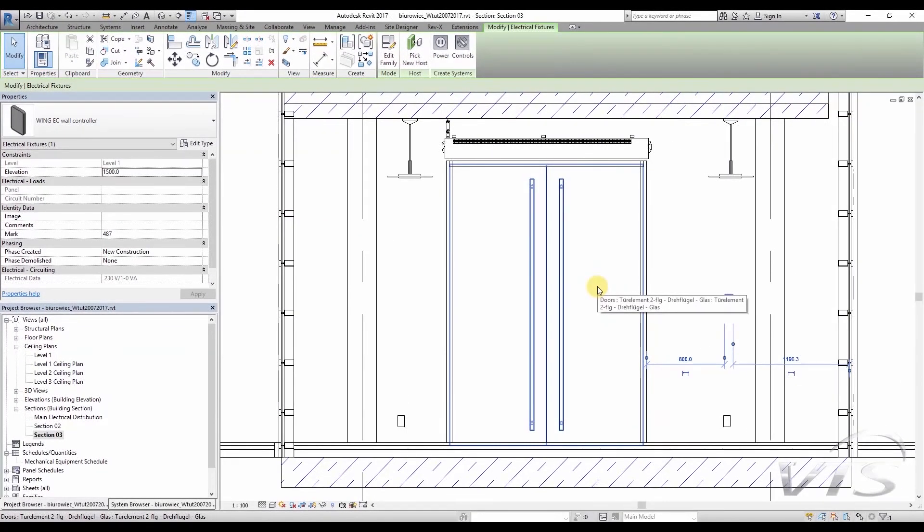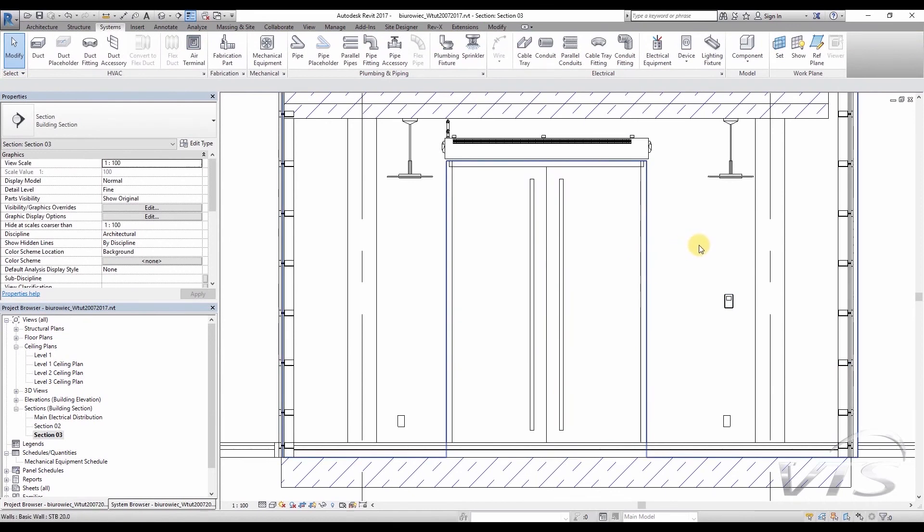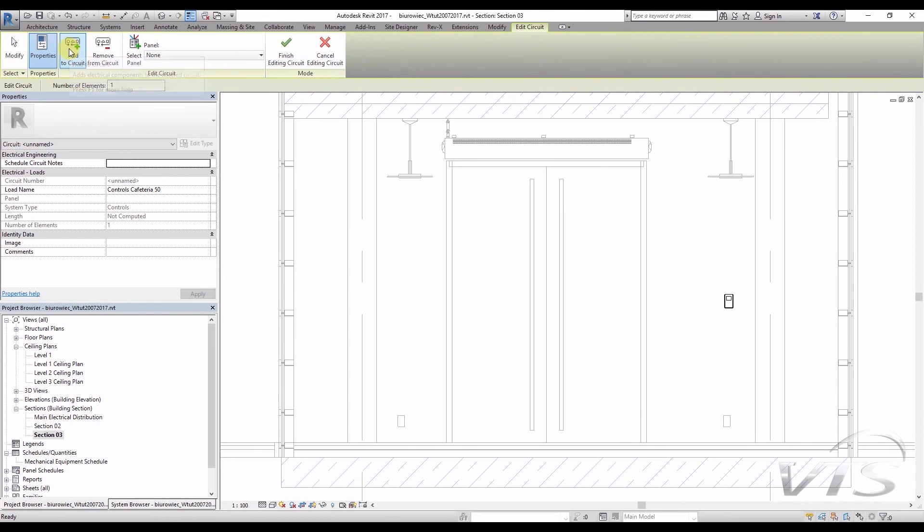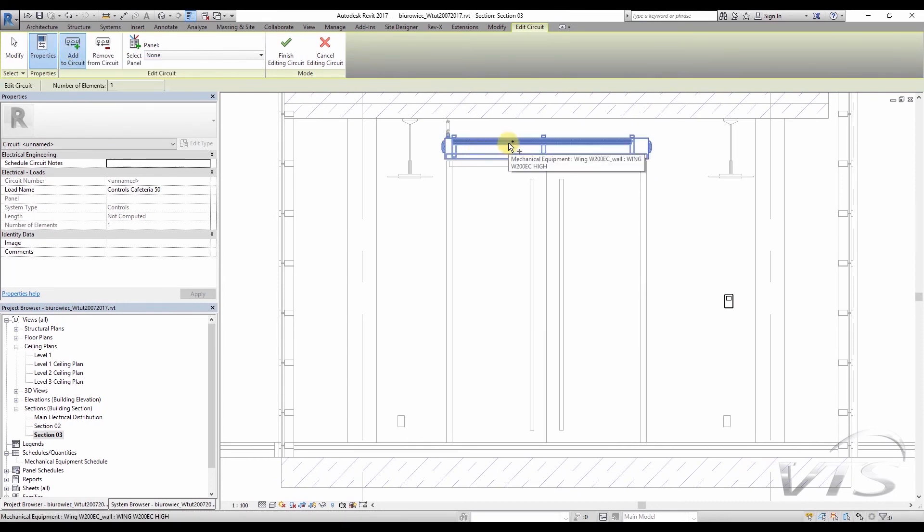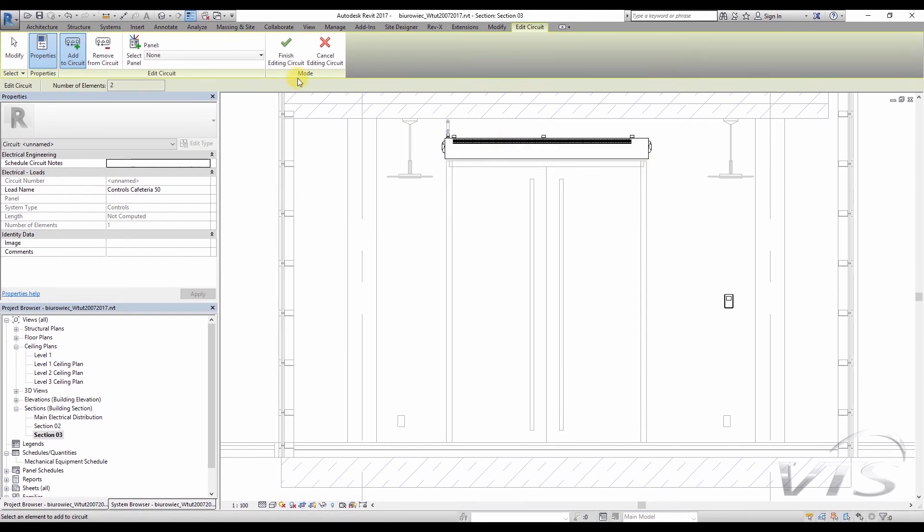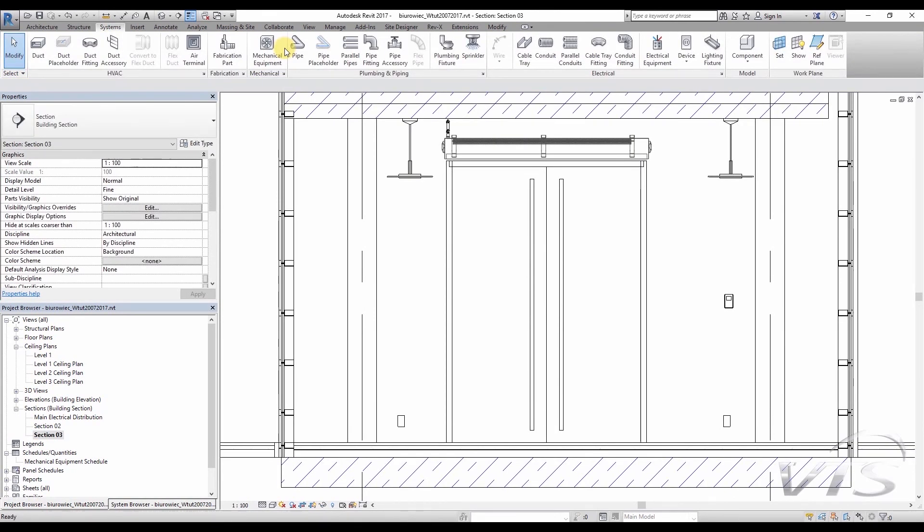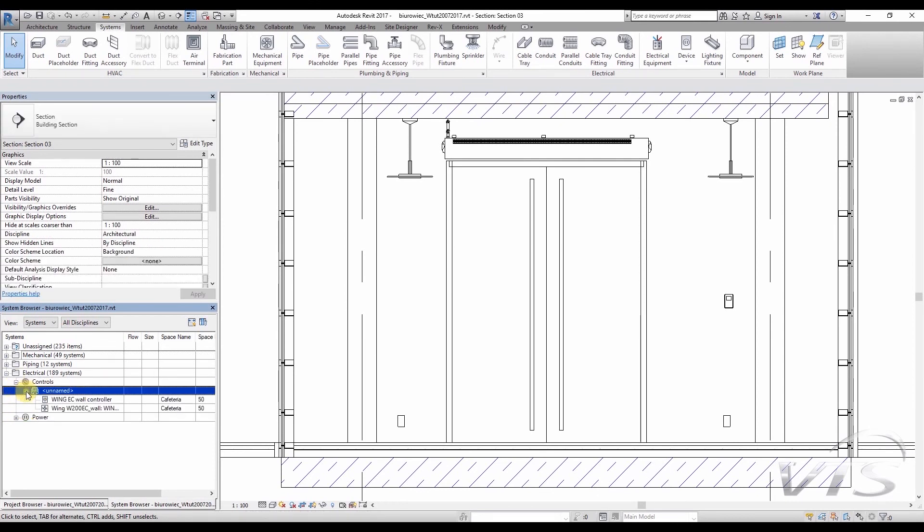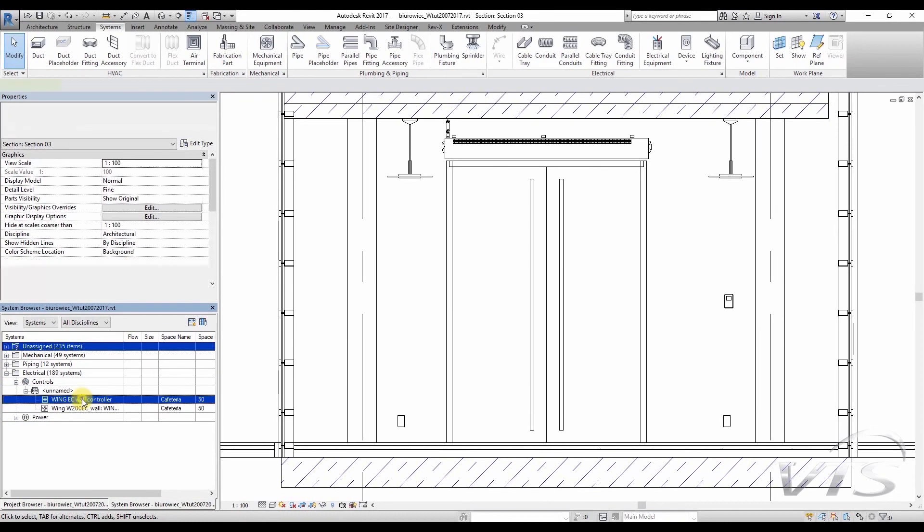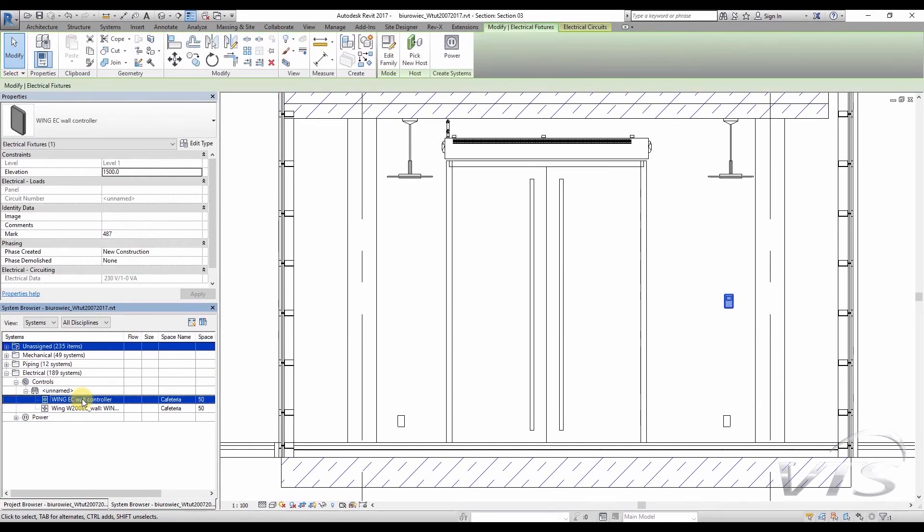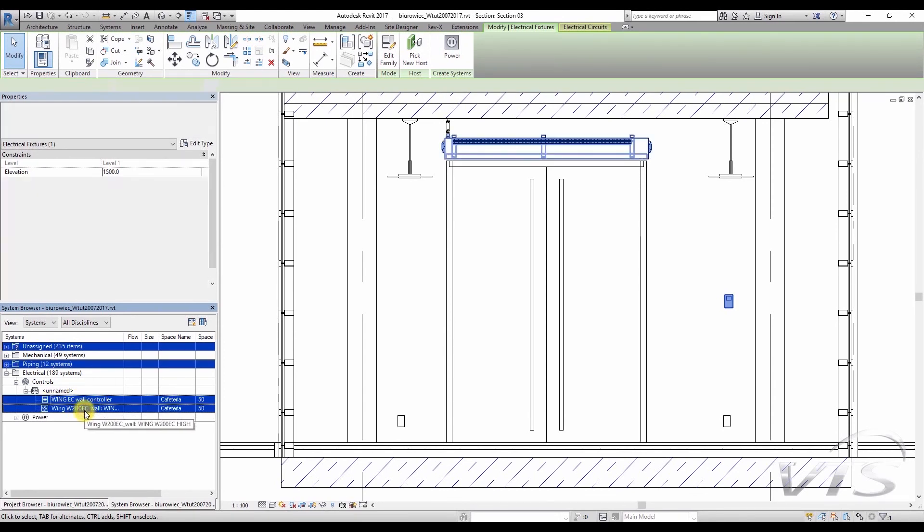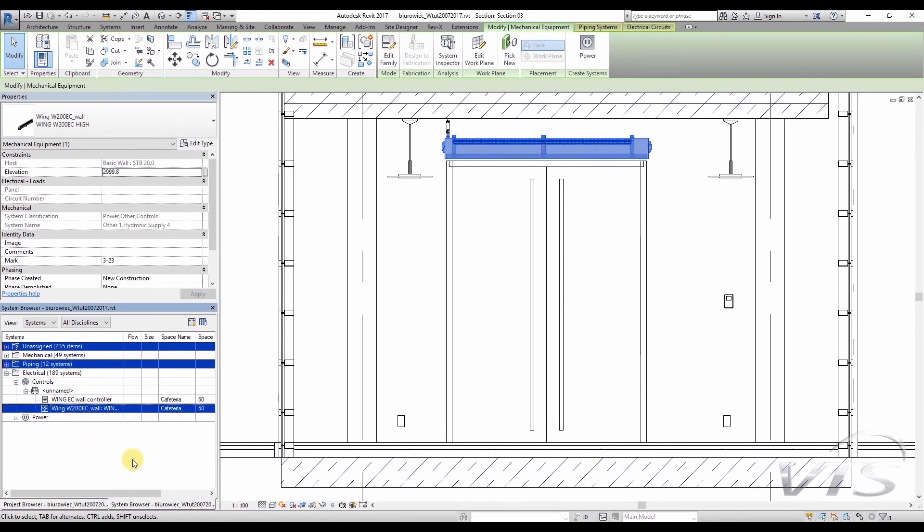Now, we only have to join these two devices into one circuit. I select the controller, and then I choose the Controls button and Add to Circuit on the ribbon. It indicates the device which shall be controlled from the level of this controller, in other words, the wing air curtain. If we have selected all devices, we click Finish Editing Circuit in order to complete the process of defining the electrical circuit. And now we just have to find an appropriate circuit in the system browser. We can see that we have two devices connected together, Wing EC Wall Controller and Wing W200 EC Air Curtain. We have connected only one curtain with the controller. However, up to eight devices can be connected to each controller.